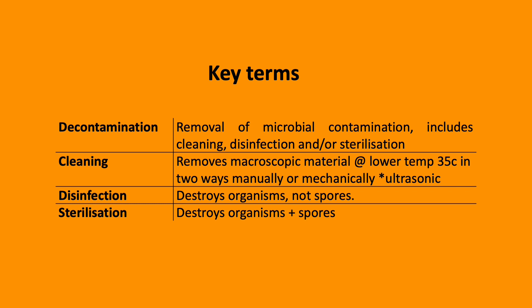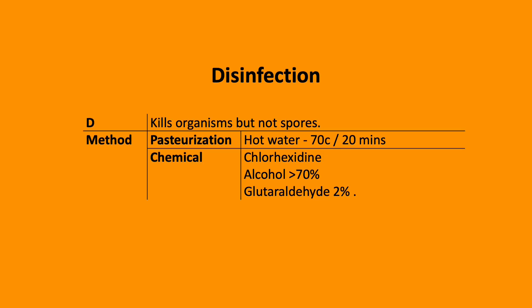Disinfection destroys organisms but not spores, while sterilisation destroys organisms including spores. Disinfection includes pasteurisation — using hot water at 70 degrees C over 20 minutes — or chemical measures, for example chlorhexidine, alcohol and glutaraldehyde.